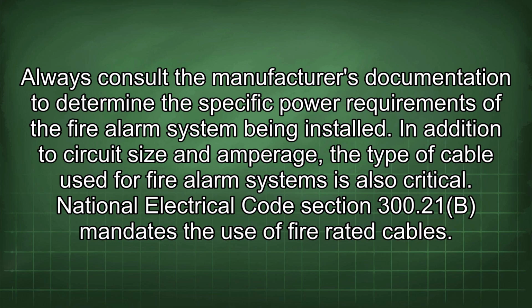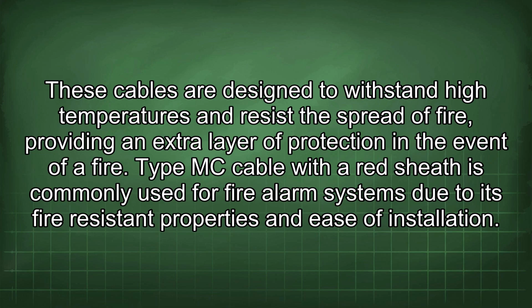In addition to circuit size and amperage, the type of cable used for fire alarm systems is also critical. National Electrical Code Section 300.21b mandates the use of fire-rated cables. These cables are designed to withstand high temperatures and resist the spread of fire, providing an extra layer of protection in the event of a fire.